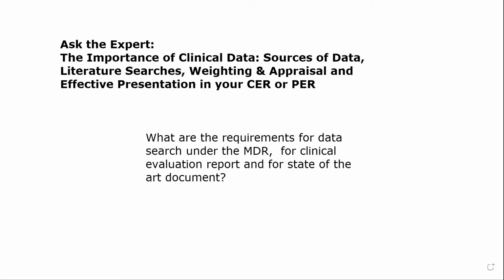The 2 that I'm going to talk about next are the competitor device and the subject device. Those are 2 separate searches. Because you are extracting data from those, there is a lot of very rigorous documentation that both MDR and IVDR require, because MedDev 2.7/1 Rev 4 requires it. So these are the requirements for data searches for MDR and IVDR compliant documents.